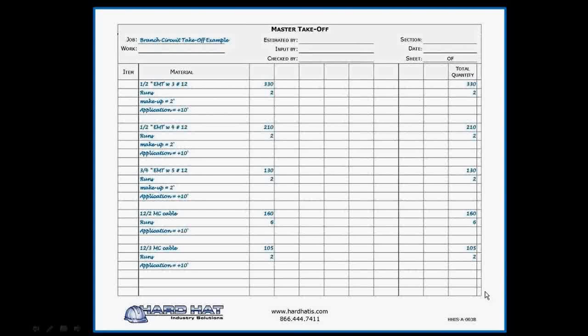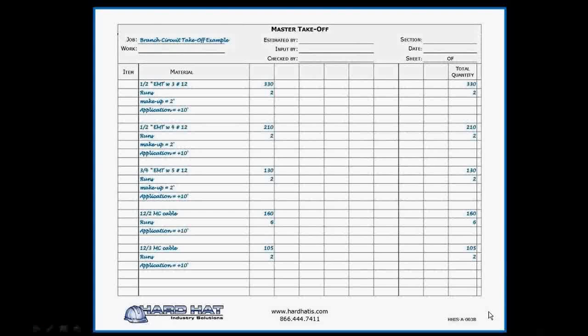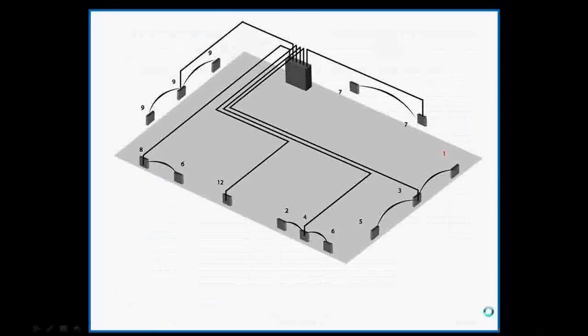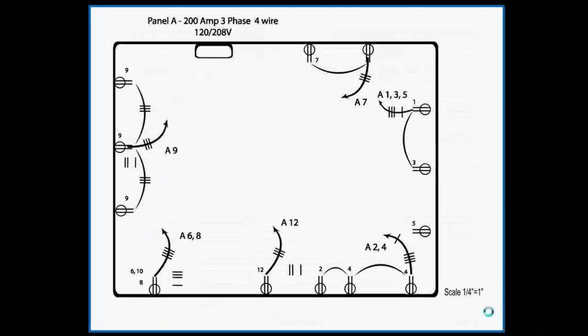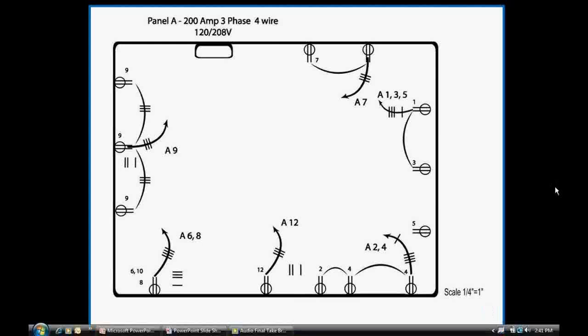Now back to the drawing to measure the next run. I make sure to reset the Scalex to zero to measure the next conduit runs. I notice that the conduit feeding circuits A2 and 4 plus circuits A6 and 8 would require half-inch EMT with four number 12s. So I take that off next. I'll circle it here.